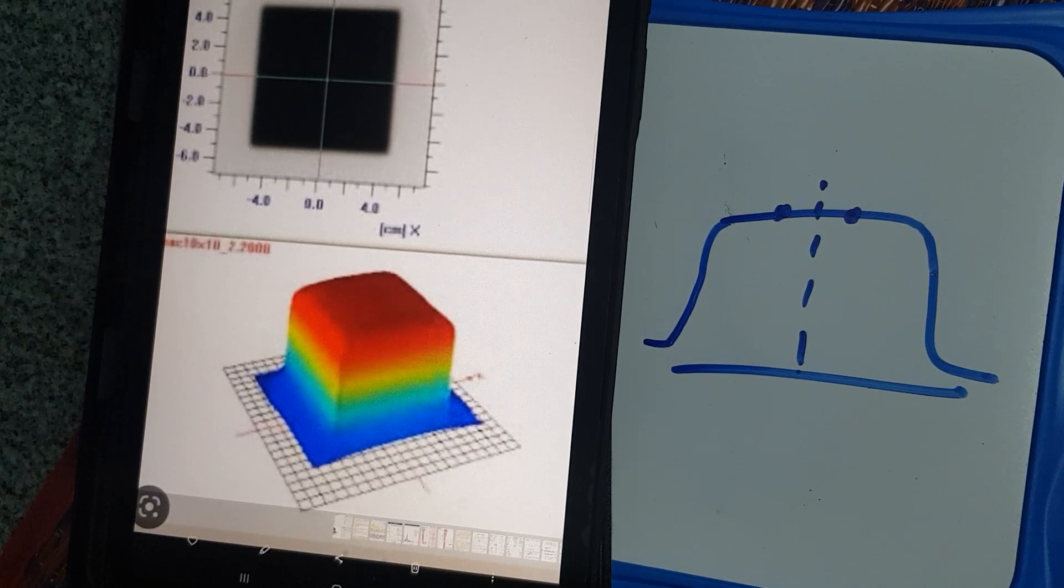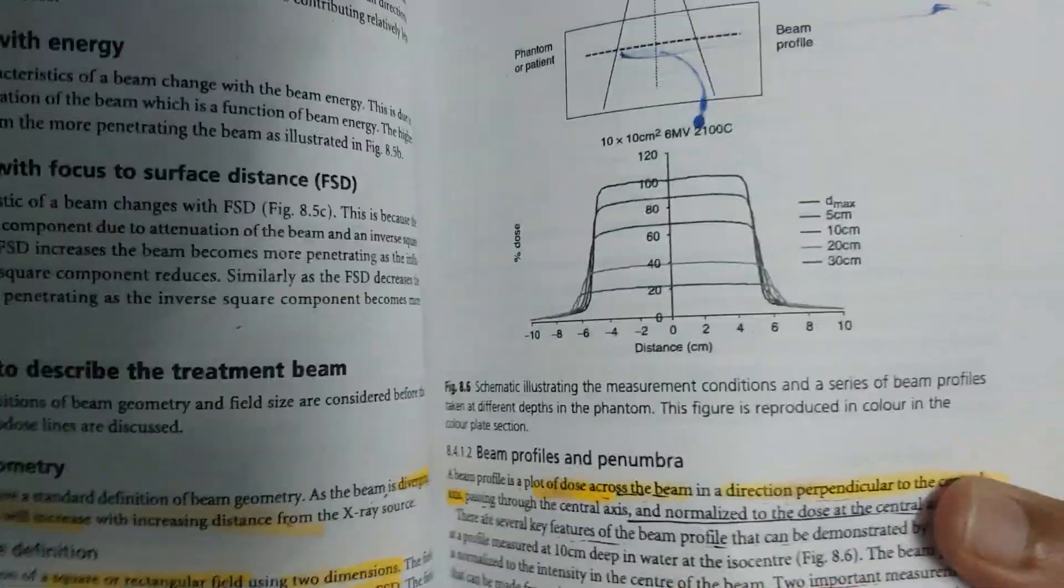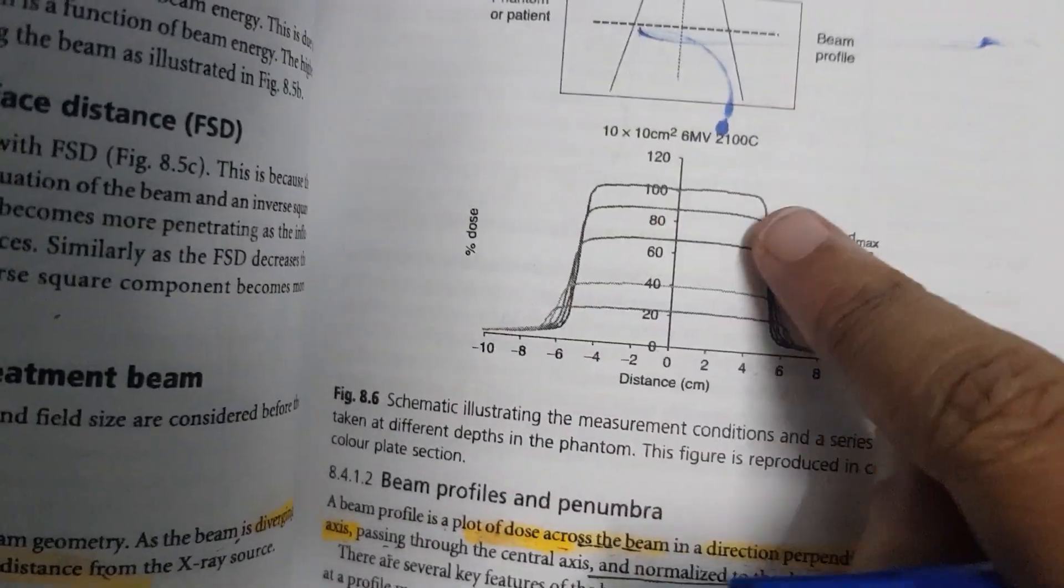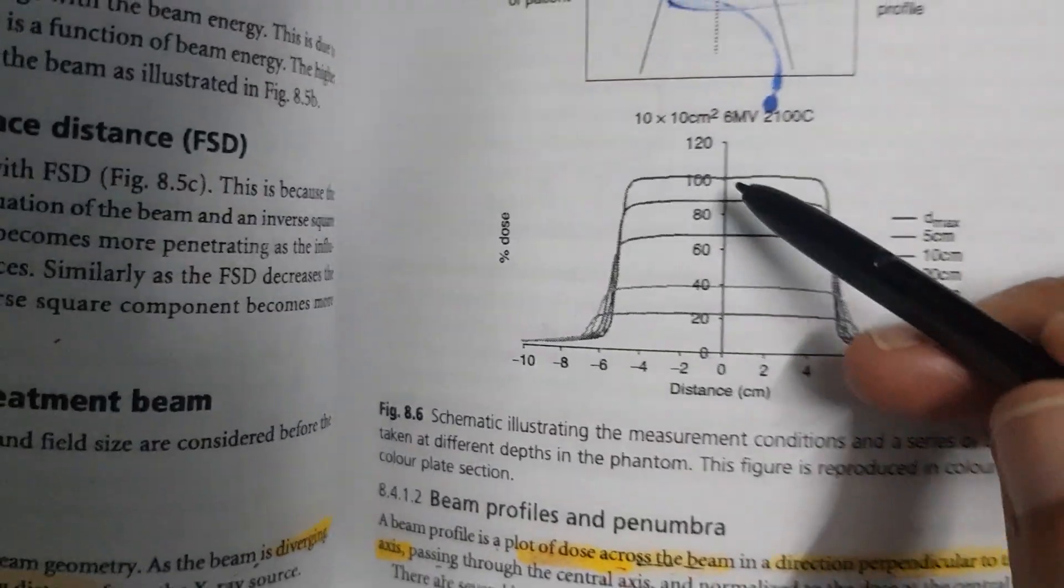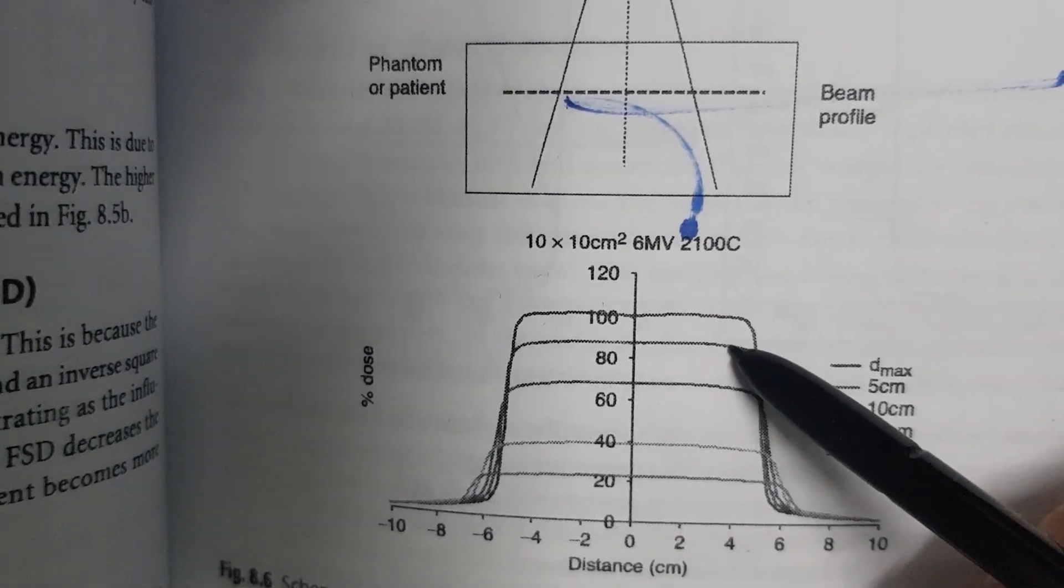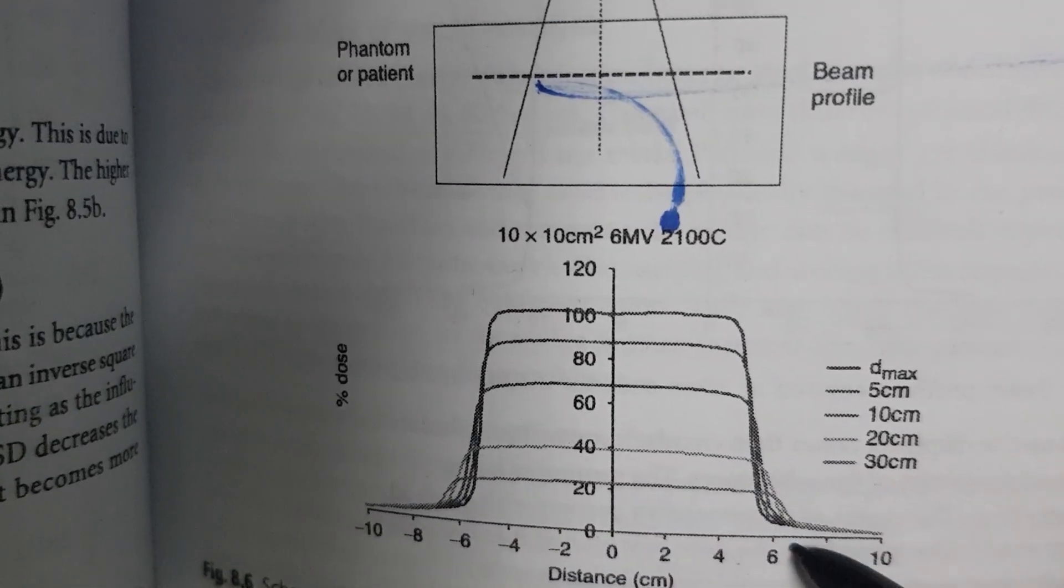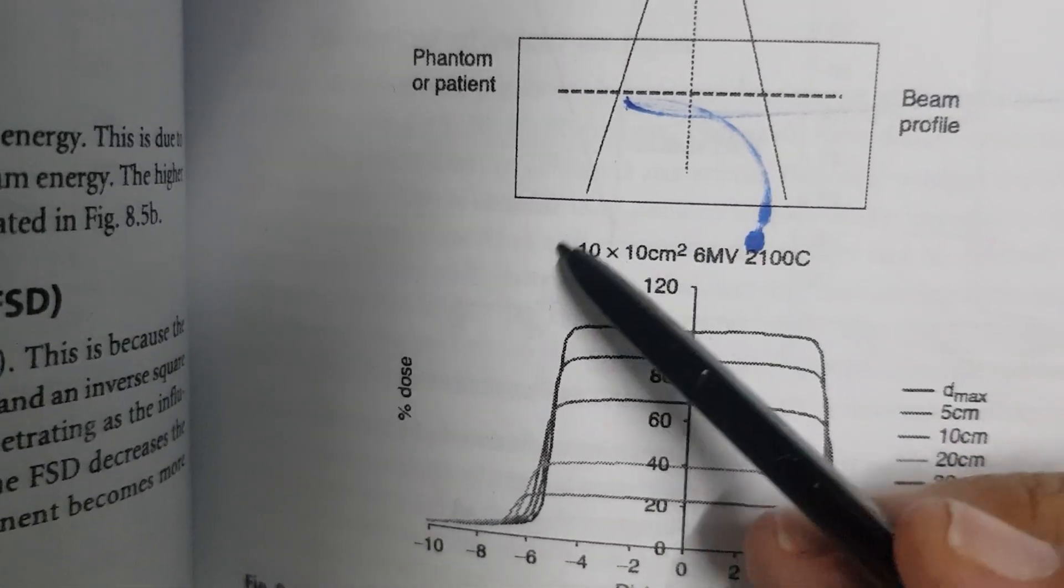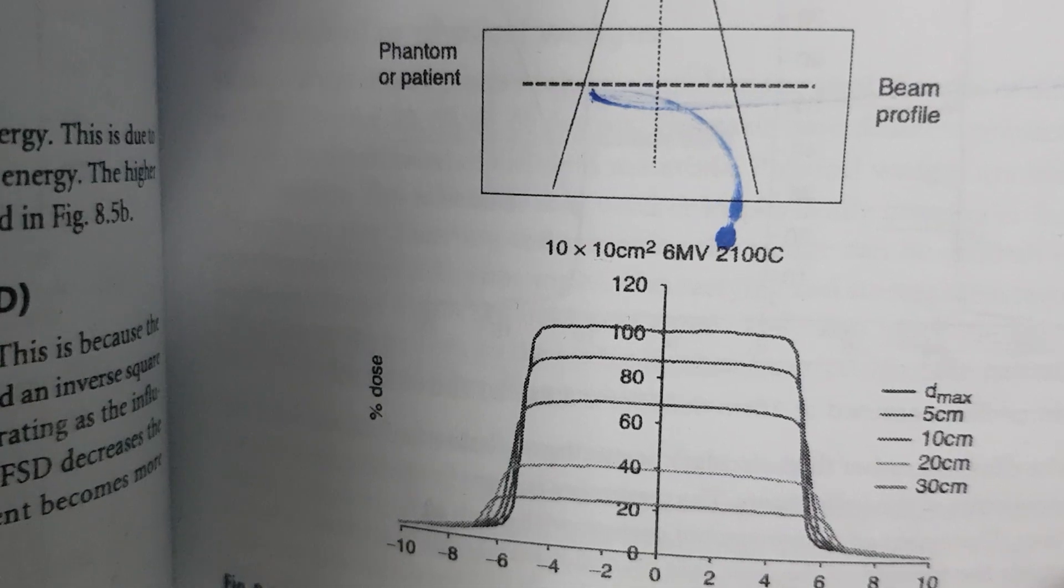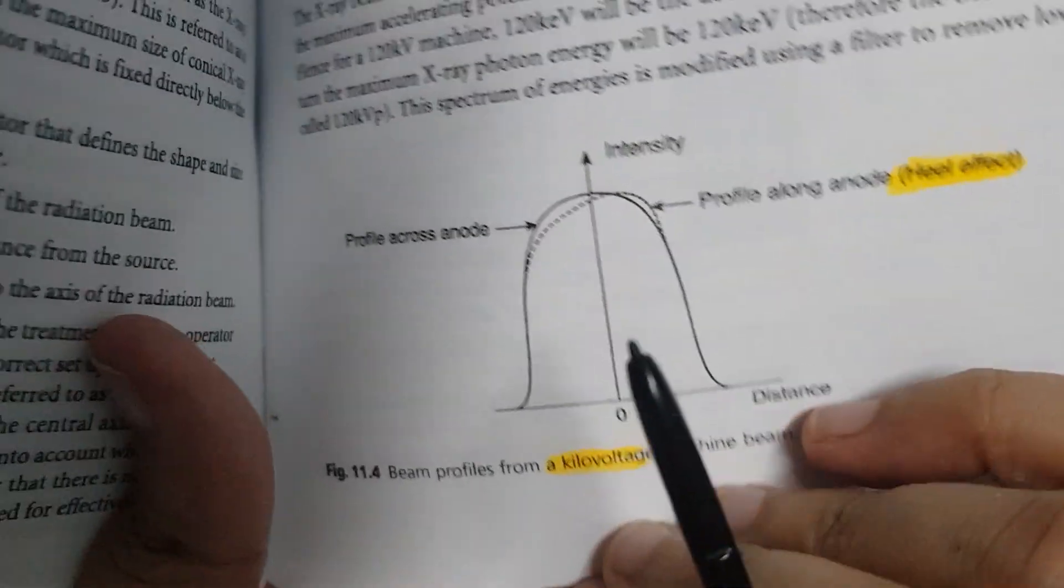If you take this as an example, here if you take this is at the Dmax level, then this is at 5 centimeter depth, then this is at 10 centimeters, this is at 20, this is at 30 centimeters. That's the beam profile, and this is for a field of 10 into 10 centimeters for a 6 MV linac.